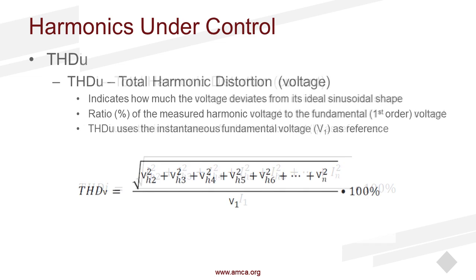When we look at THDU or THDV, we use V in America, but in Europe we use U. This is your total harmonic distortion voltage. So similarly, it's indicating your voltage and how much it's deviating from your fundamental voltage. And this is the ratio of your measured harmonic voltage to your fundamental first order. Similar formula, but now we're looking at voltage instead of current.